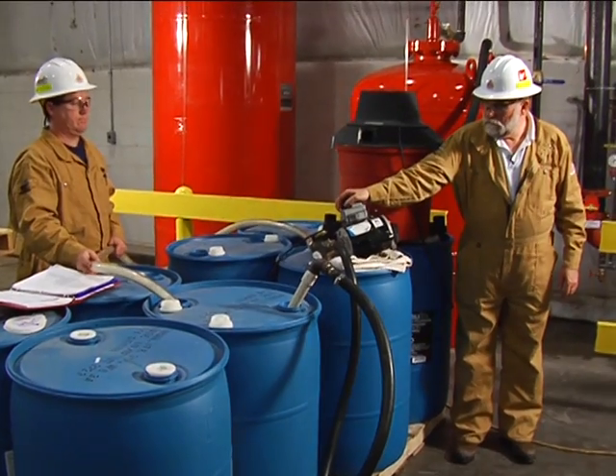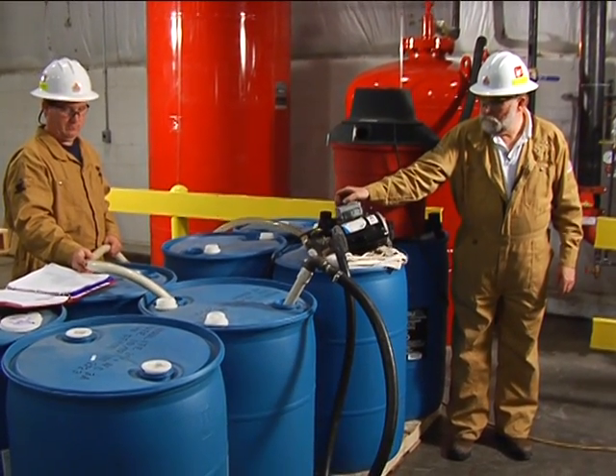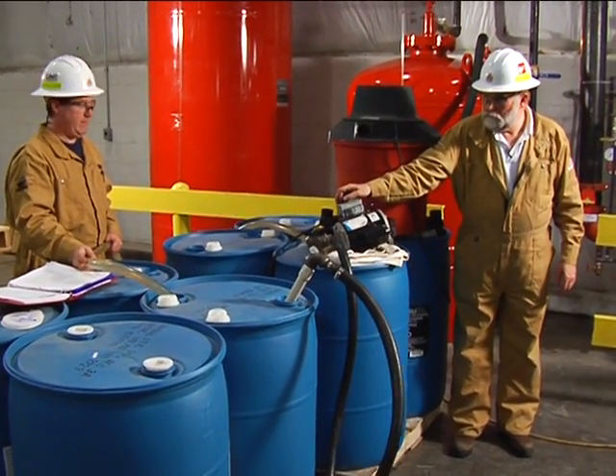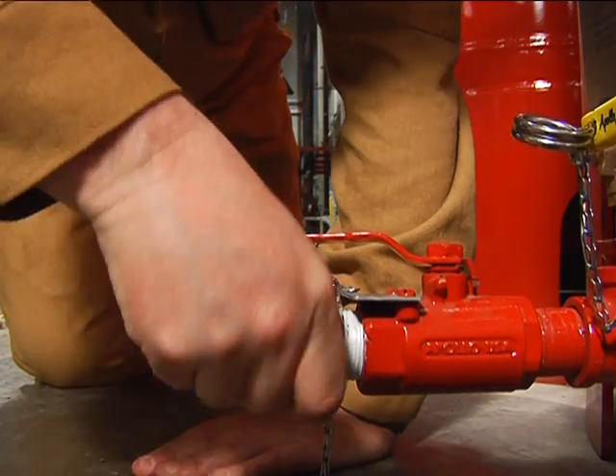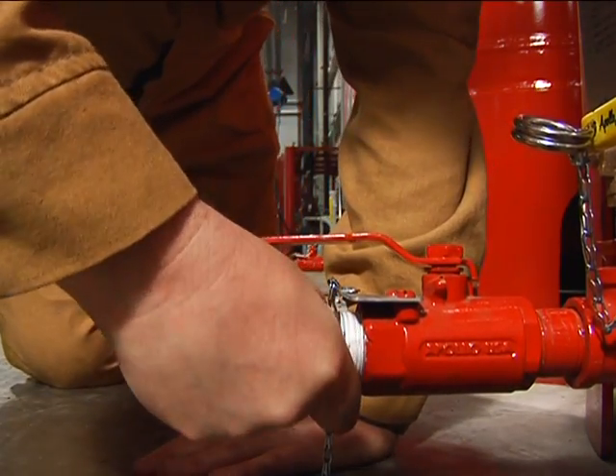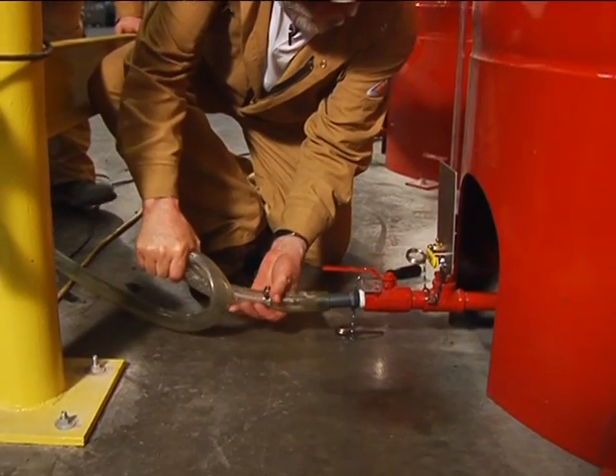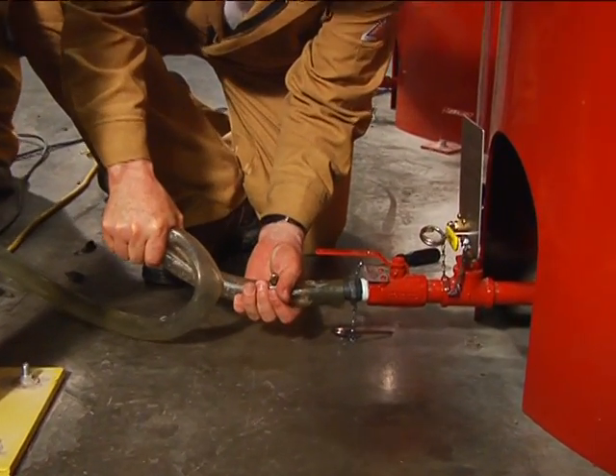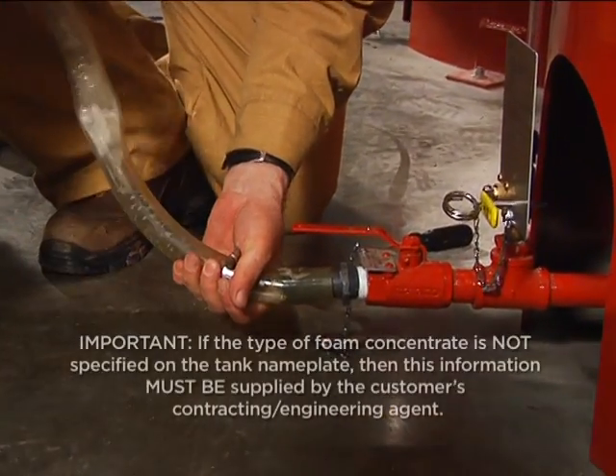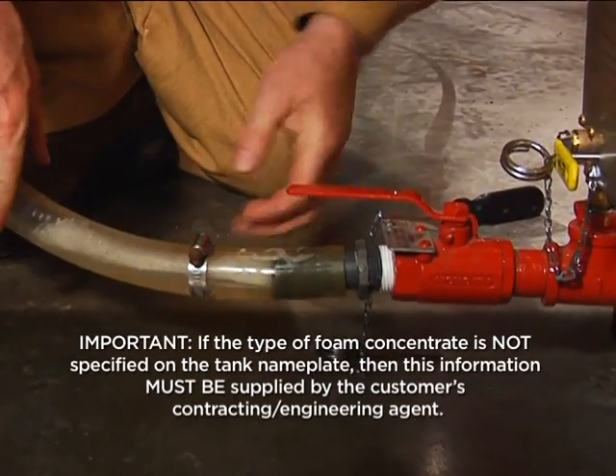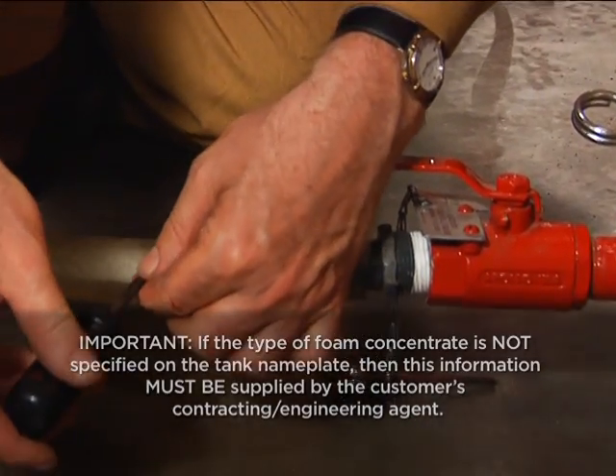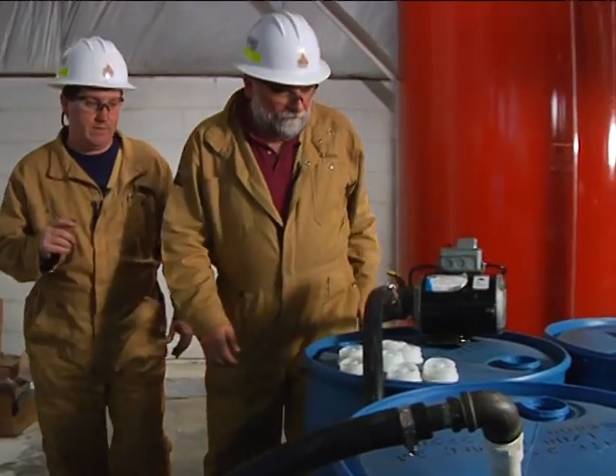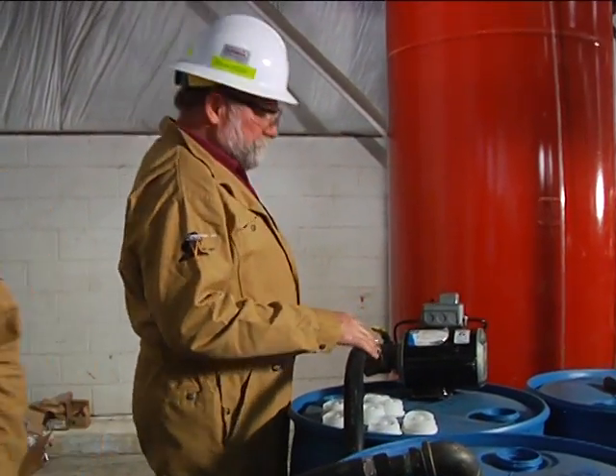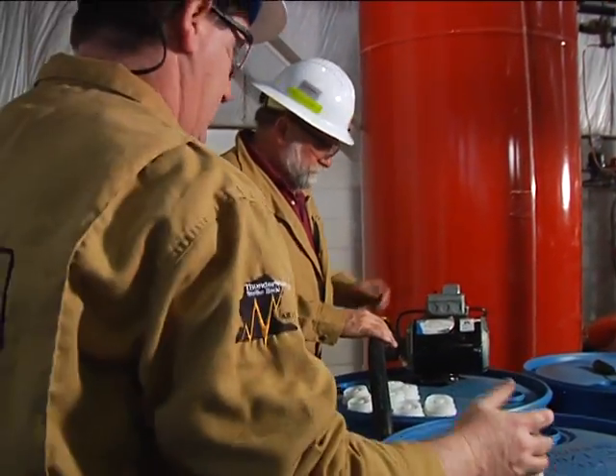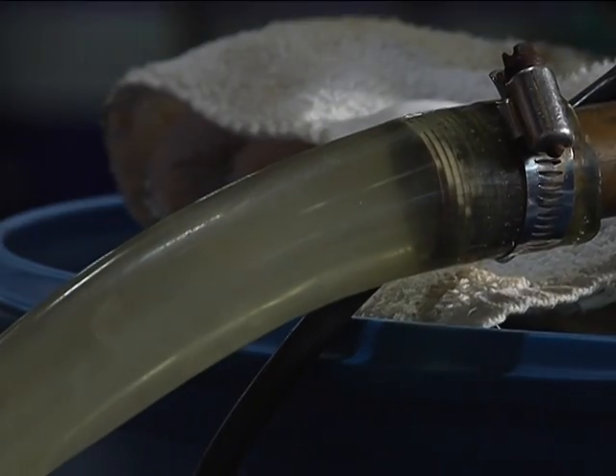Next, open the pump valve and prime the pump with concentrate, then close the pump valve. Now, connect the concentrate pump to the bladder drain fill valve. Again, only the Ansul foam concentrate specified on the tank nameplate may be pumped into the bladder. Start the concentrate pump, open up the pump valve, and then open up the bladder drain fill valve. Now you can proceed to fill the bladder tank with concentrate.